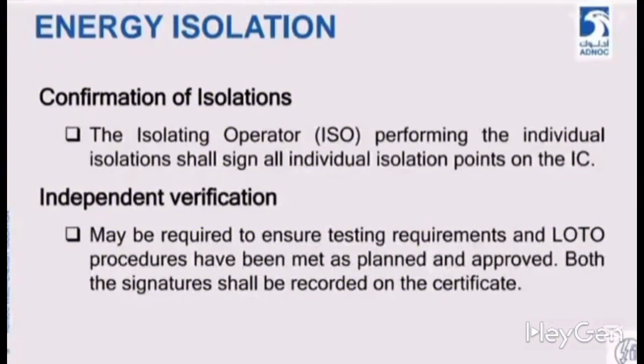We can use a bleed valve, though, use a gauge, or operate the electric component to use it. Independent verification is also required to ensure testing requirements are met and the LOTO procedure is aligned again with the plan and approved procedures. Both signatures shall be recorded on the certificate.